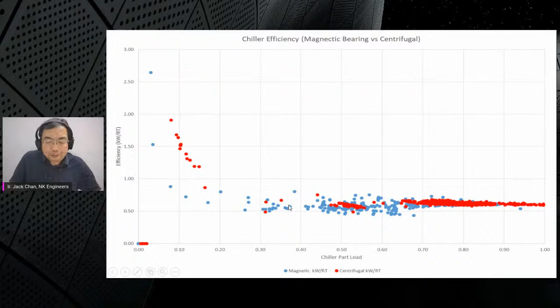So again, it's up to the owner. If your building is always operating at full load, always occupied, then it doesn't really matter if you go for magnetic bearing or centrifugal chiller. But if a building is going towards lower end loads, if you can't occupy your building that much, then it's better to go for a magnetic bearing chiller. So that's all — get the most efficient chiller you can afford.